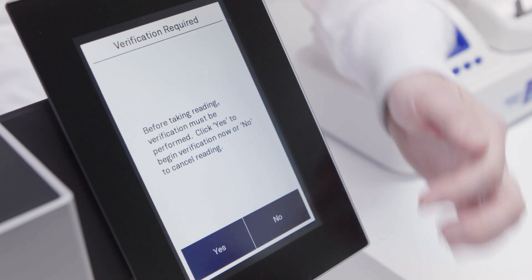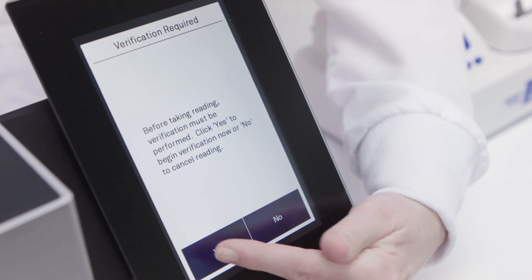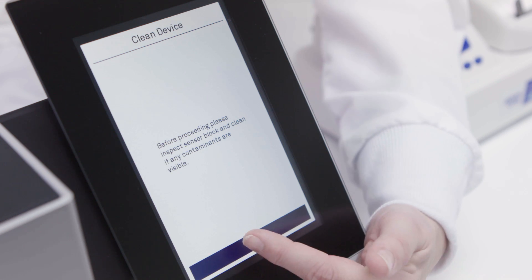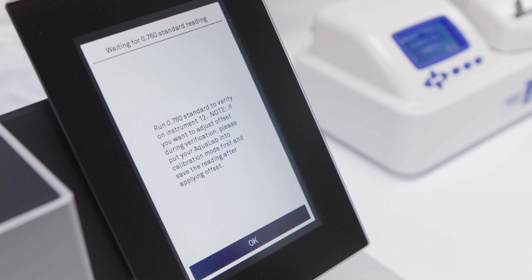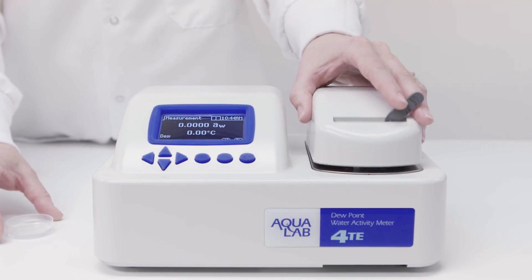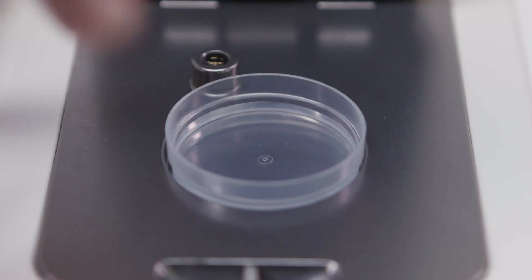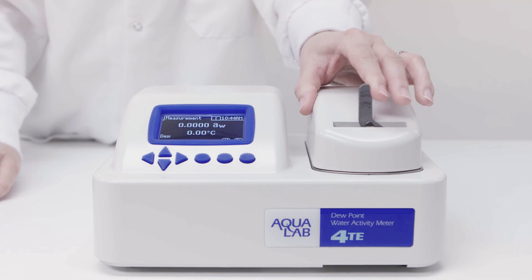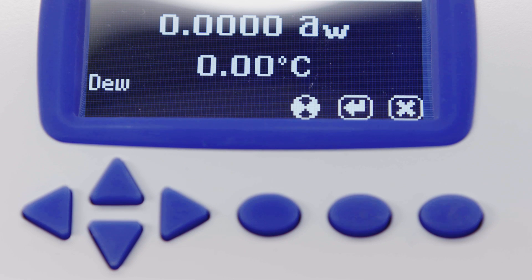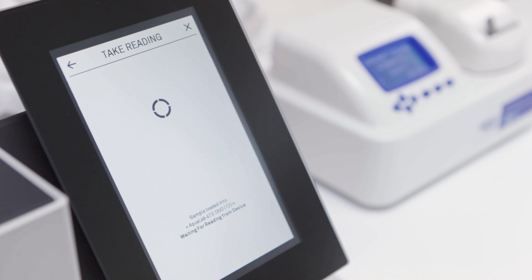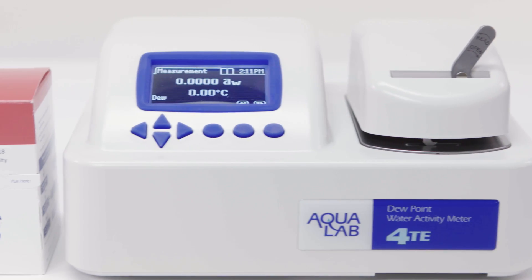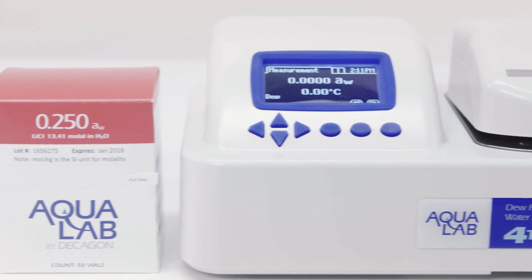Let's move on to verification of the instrument. The safety and quality of your product depends on its water activity reading, and the quality of your water activity reading depends on the performance of your water activity instrument. It's not something you want to take for granted. Fortunately, you can use salt solutions with a known water activity to verify that your instrument is performing correctly. Often these verifications need to be documented and auditors and inspectors will expect to see these values.